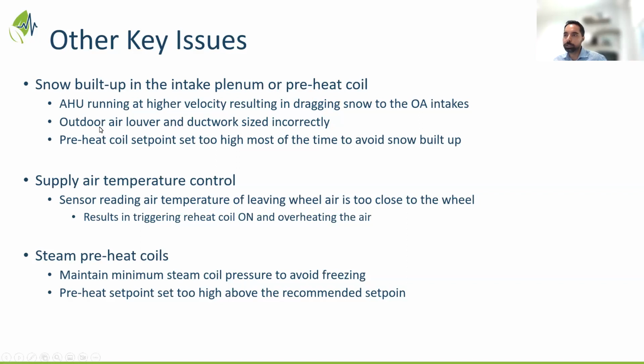So there's one of the sites where we're currently doing a pilot to see how we could mitigate this effect of snow build-up for the majority of the heating season. There are going to be days when the snow will start to accumulate, but what other things could we do to make sure this snow accumulation doesn't happen? We can use technology that reads the weather and bumps up the preheat temperatures if needed for those particular days, and still use the lower preheat set point for the rest of the period, because that's where we're going to get most of the savings. So that's a pilot that's going to be tested in October this year.